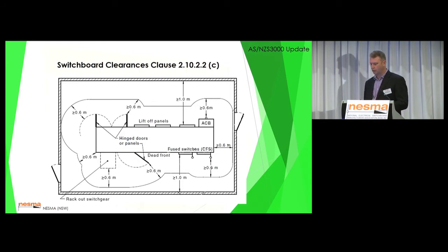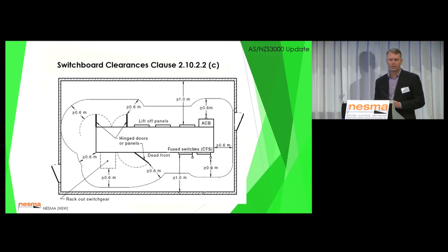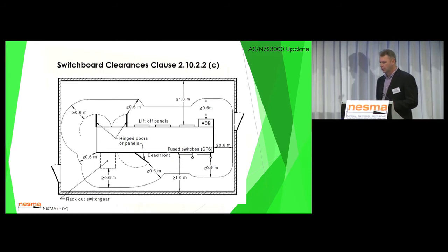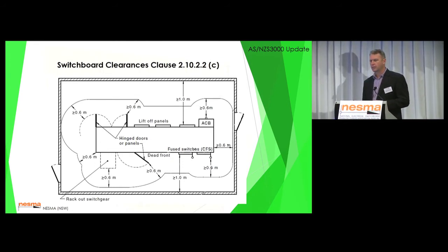As you can see, the withdrawn section, the bottom left, is a rack-out switchgear. Still has 1 metre from the usable face, the closed face of the switchboard, but 600 clearance from the racked-out position.